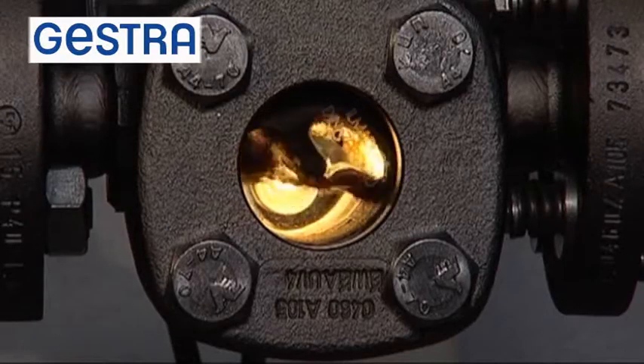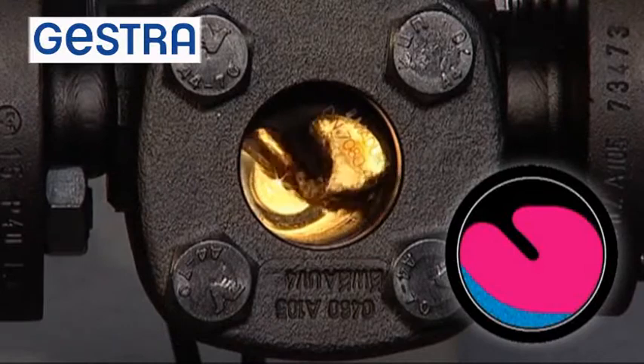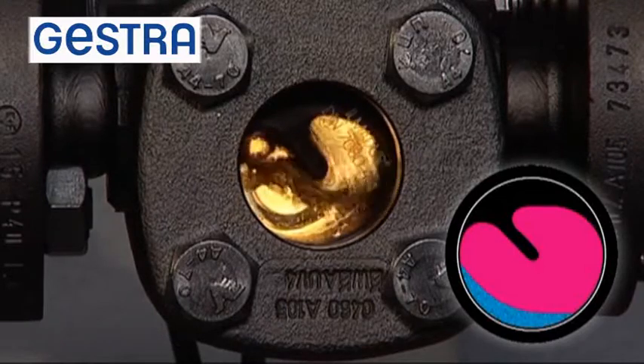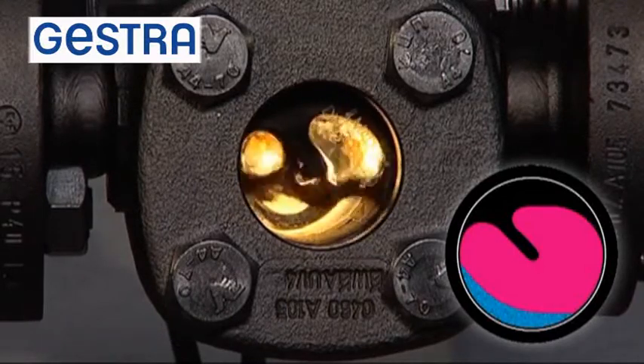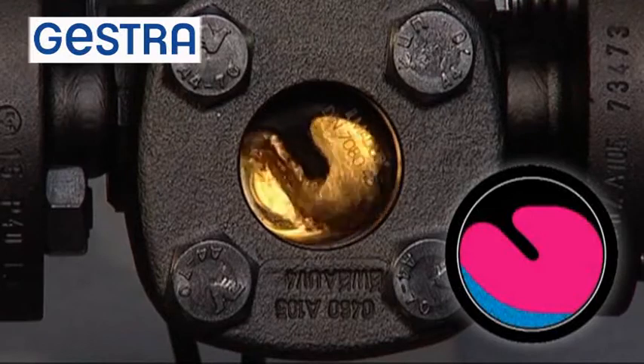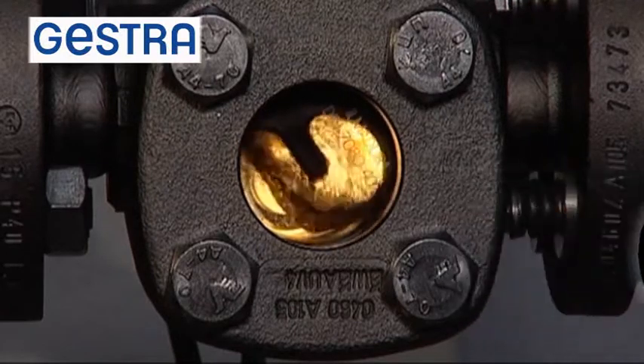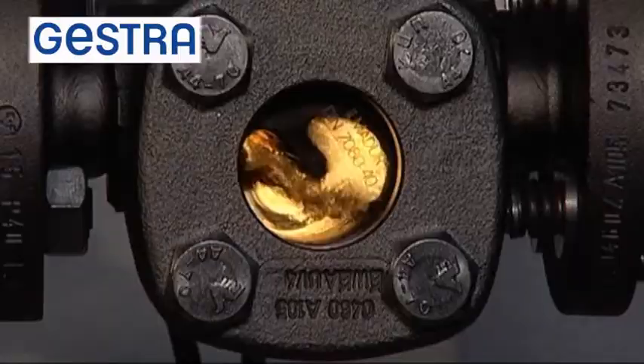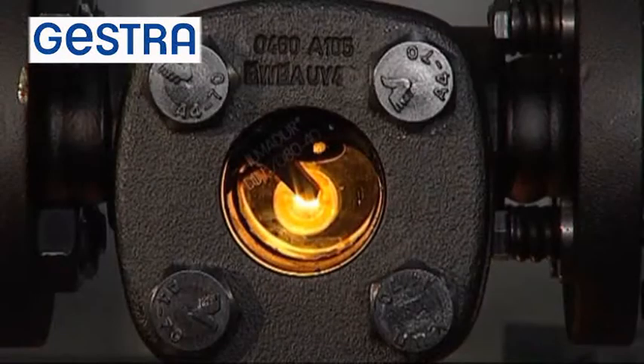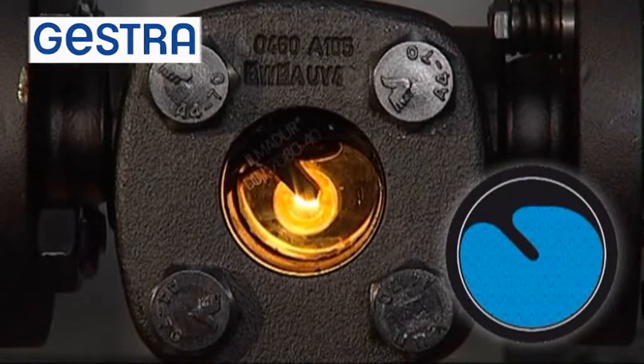However, if a steam trap is faulty and causes any loss of live steam, the situation changes. The deflector emerges from the water, since the steam now passing through tends to press the condensate downwards into the siphon. This is a clear indication that the steam trap is causing loss of steam. Here, the Vaporscope is completely filled with condensate, which points to a banking up of condensate in the trap.